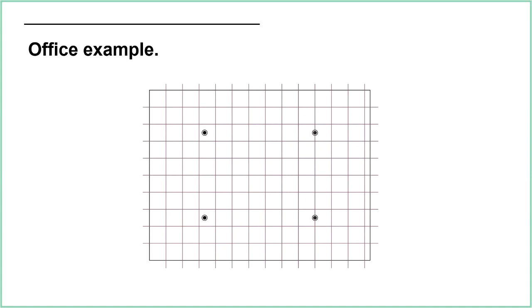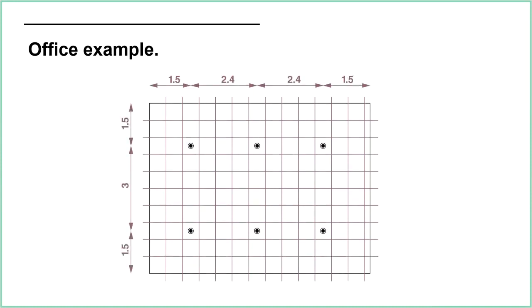Because these heads are at the absolute maximum, even moving them just 10mm means we have to introduce more sprinkler heads. Now we've got six heads rather than four. I've changed the spacing — keeping three meters north to south, but east to west changed to 2.4m, going 1.5m to walls, staying within the general confines of not closer than two meters and no further than four meters apart.